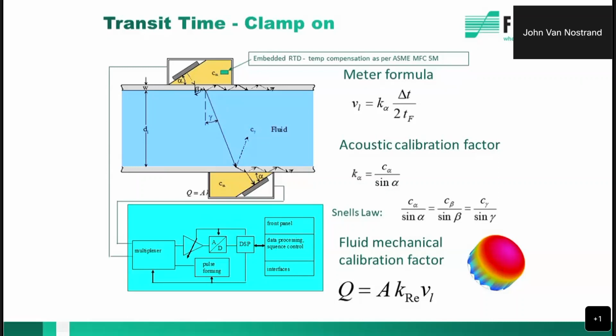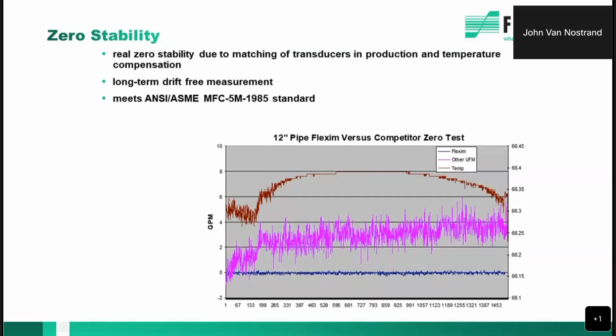So the placement of the transducers can also require a different spot as the temperature changes throughout the day, which is why often other clamp-on meters lose their signal. So we did a quick test. We wanted to prove that this was true, and we basically put our meter on a capped piece of pipe with another set of transducers from another leading manufacturer on that same piece of pipe.